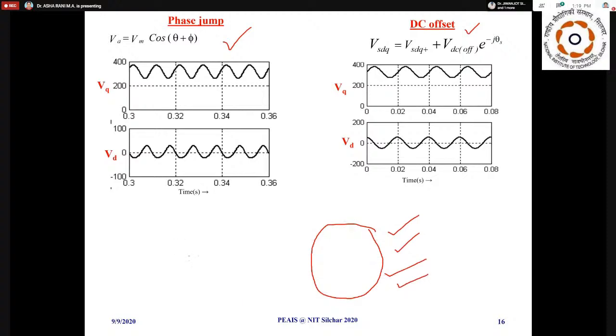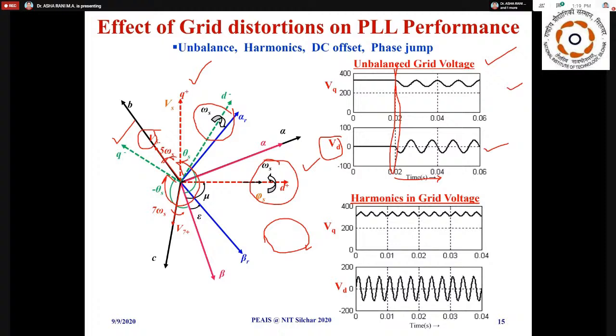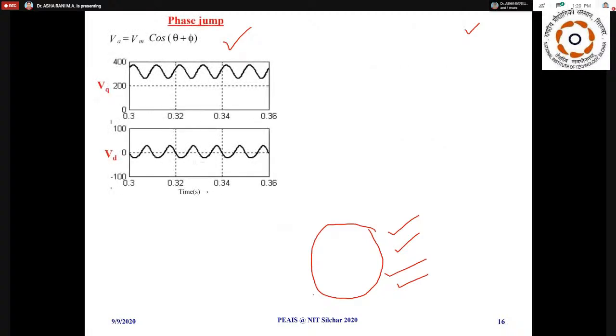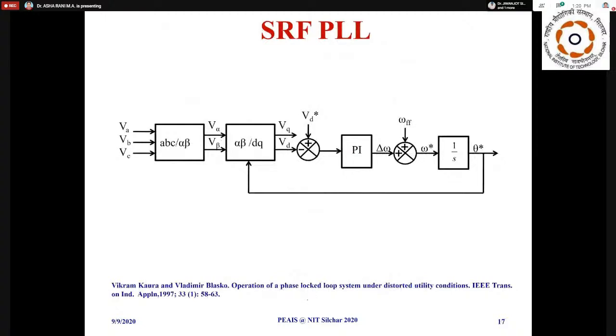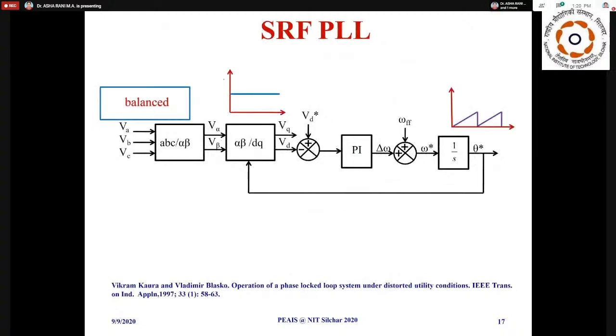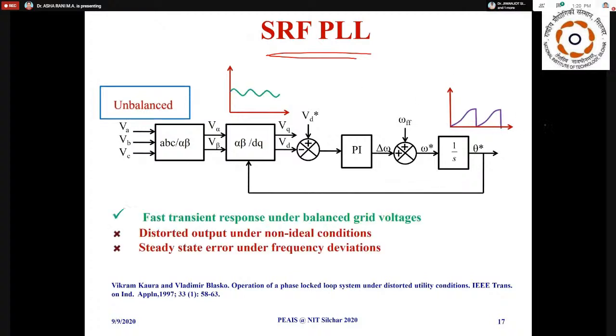Why do harmonics produce a 6 omega term? It is the relative frequency, because 5 omega is in one direction and omega is in the other direction. So the relative frequency is omega s minus minus 5 omega s, which ultimately becomes 6 omega. These things we have to take care of. Such a fundamental PLL will not help in grid synchronization. If you have a balanced system, we assume VD will be constant and you get a proper PLL output. Whereas if the grid is unbalanced, the PLL output will also be distorted. So this kind of scheme can give fast transient response under balanced grid voltages, but under distorted grid conditions it will not give proper output.